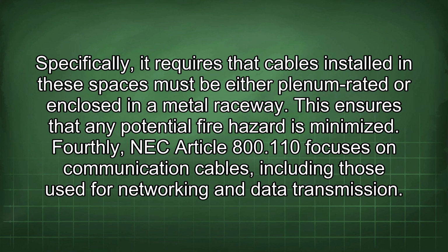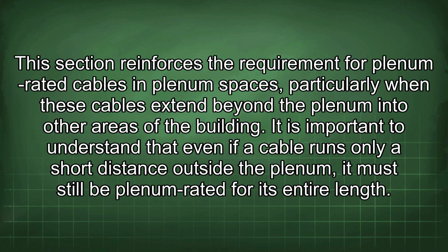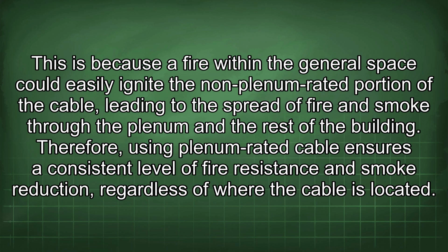Fourthly, NEC Article 800.110 focuses on communication cables, including those used for networking and data transmission. This section reinforces the requirement for plenum-rated cables in plenum spaces, particularly when these cables extend beyond the plenum into other areas of the building. It is important to understand that even if a cable runs only a short distance outside the plenum, it must still be plenum-rated for its entire length. This is because a fire within the general space could easily ignite the non-plenum-rated portion of the cable, leading to the spread of fire and smoke through the plenum and the rest of the building. Therefore, using plenum-rated cable ensures a consistent level of fire resistance and smoke reduction, regardless of where the cable is located.